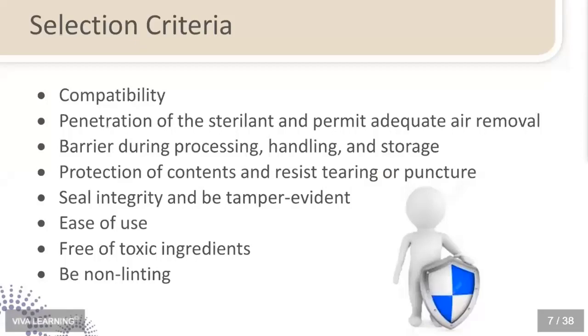Be non-linting. You don't think about this very often, but I've talked to our sterilizer technician friends, and one of the things they're seeing with repairs or maintenance issues is filters and valves getting clogged with lint. So you want to make sure that the materials you're putting in there every day are not going to cause any additional lint going through the sterilization process. Also, please, please do not put any type of over-the-counter paper towel on the bottom of the tray of your sterilizer to try and help with any type of water condensation. Those paper towels are not approved to be used inside a sterilization device and definitely will cause linting issues.